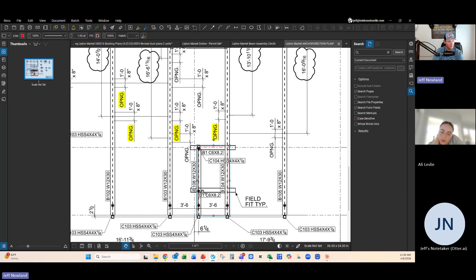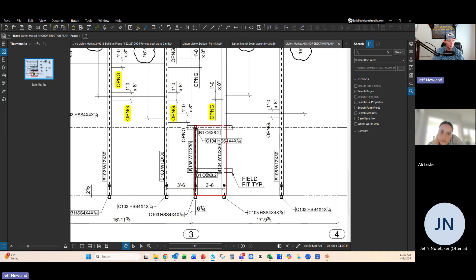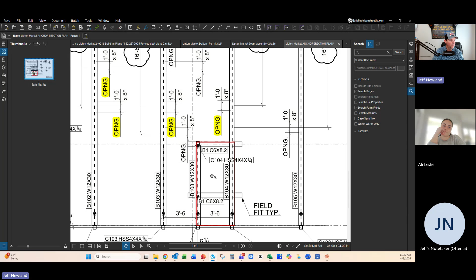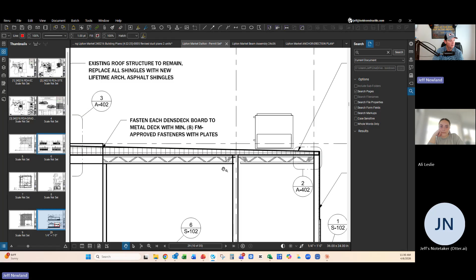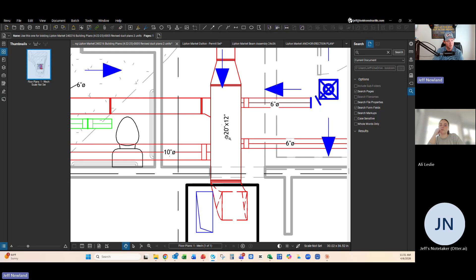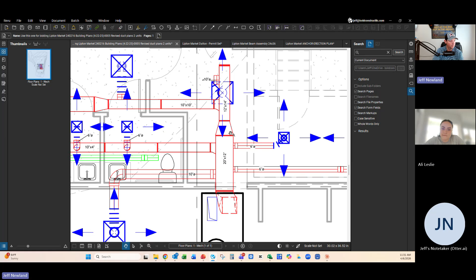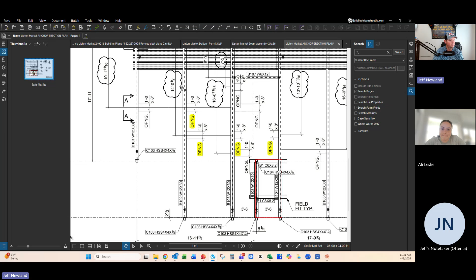Your HVAC unit will actually sit right here, that's why there's reinforcement here—see, it says field fit, so they'll ship this angle and wherever it needs to set, they'll weld it. This is where your HVAC unit will fit, and you've got piping, so you kind of go back to this drawing. That's where it's setting—you've got this big trunk line, and it's only 20 inches wide to get in between the trusses. Then it runs this way, and you've got them running back this way. That's why you've got all these openings, because they're going to pass through here.